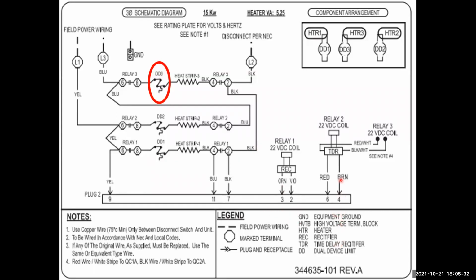We can come over, these two are tied together. So if we had two-stage heat, we'd go ahead and energize this. With 24 volts, it would get converted to the DC, 24 volts DC, and then it would come over here and power your third relay, which would close your first and second one. This would happen right away. This would happen 5 seconds afterwards, and this would happen 8 seconds after that.